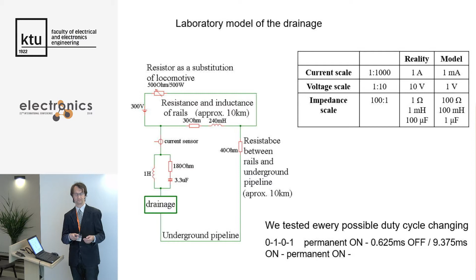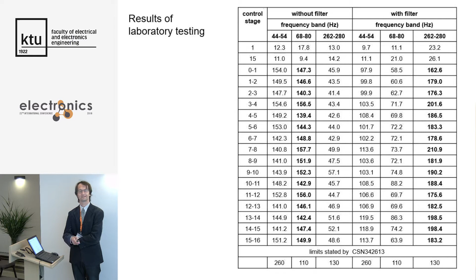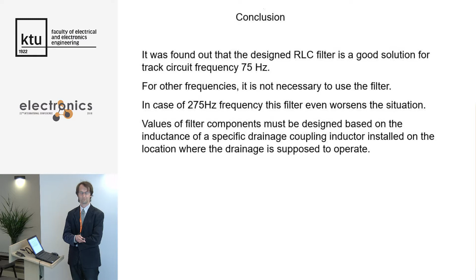Here are the results. Without filter, with only the inductor, all values in the frequency protective bands around 75 Hz were exceeded. With filter, it was okay here, but on the other hand, values in this other protective frequency band were exceeded. So the result is that for one specific frequency, for example 75 Hz, this filter can be quite a good solution to this problem. For other frequencies we must not use it, and values of components must be designed particularly for the inductor in the place where it is supposed to operate.